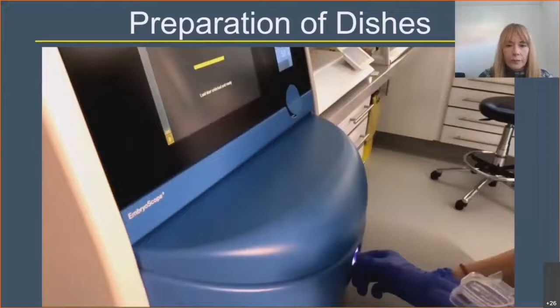So let's see some scenarios. First scenario is that there are signs of contamination present in more than one IVF case. So what would you do? Some suggestions are to prepare the dishes always under the laminar flow hood, to check the sterility of all the supplies, such as pipettes, tips, and dishes, to check the media expiration date, and to reduce the quantity of dishes, because if we prepare many dishes at the same time, many accidents may happen. We can desterilize a pipette and use it again, and then contamination can arise. And of course, to revise the sperm preparation procedures. If it's not done properly, you may have contamination.